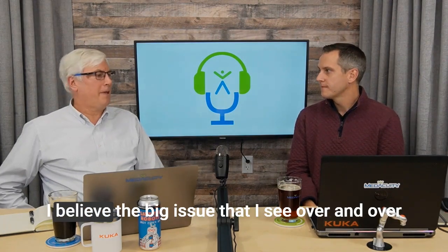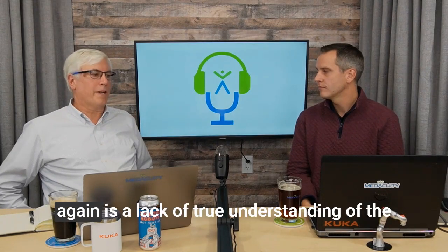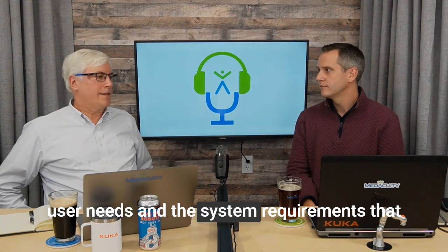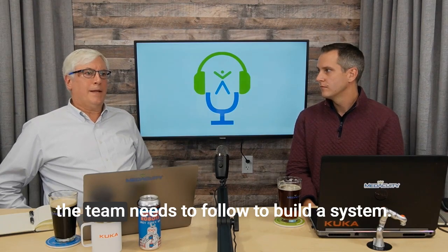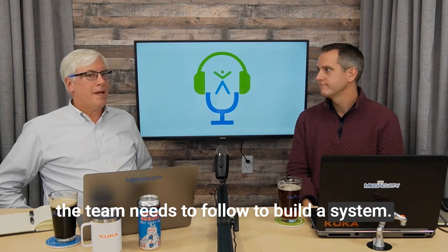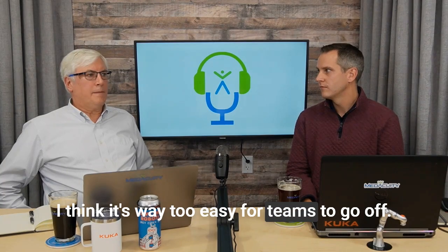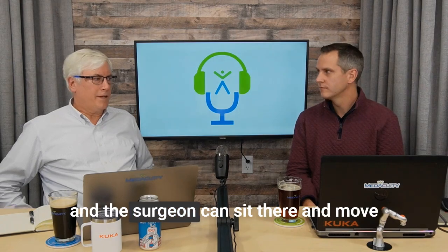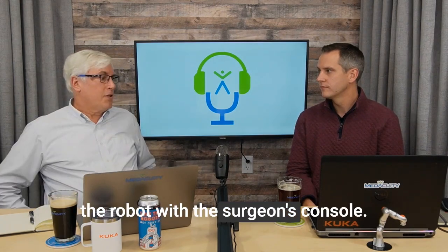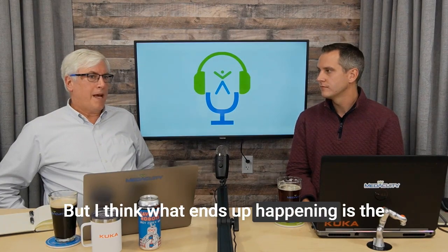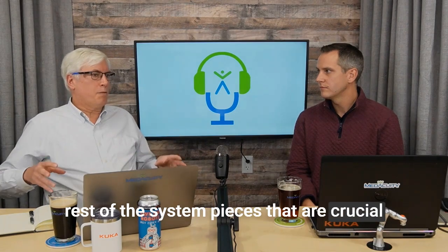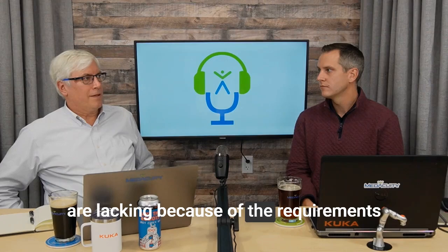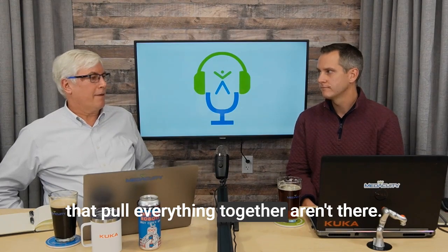Sure, Sean. The big issue that I see over and over again is a lack of true understanding of the user needs and the system requirements that the team needs to follow to build a system. I think it's way too easy for teams to go off. For example, the controls team can very quickly get the robot up and running, and a surgeon can sit there and move the robot with the surgeon's console. But what ends up happening is the rest of the system pieces that are crucial for the entire system to get through FDA are lacking, because the requirements that pull everything together aren't there.